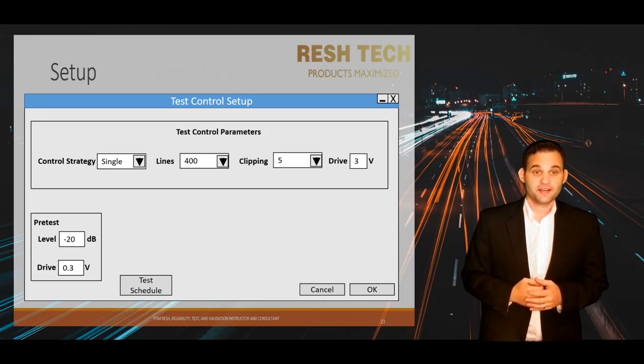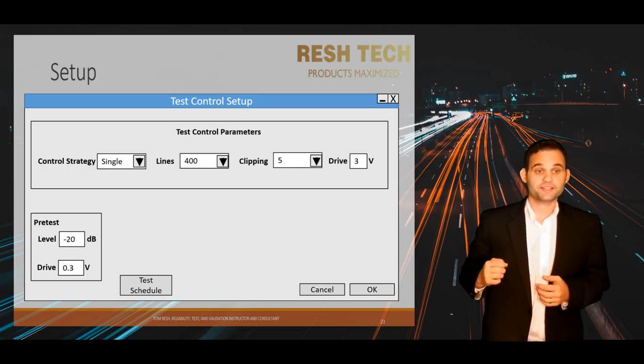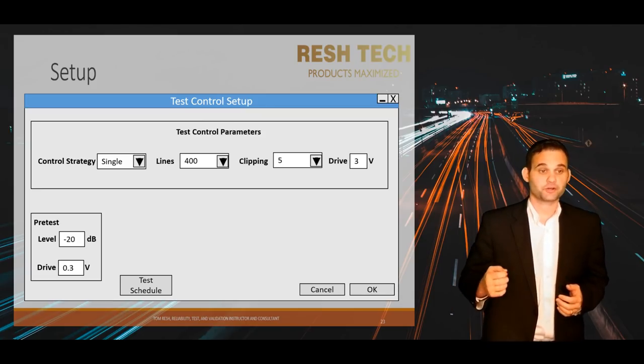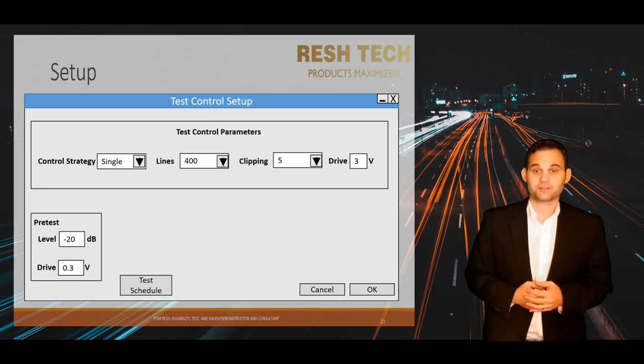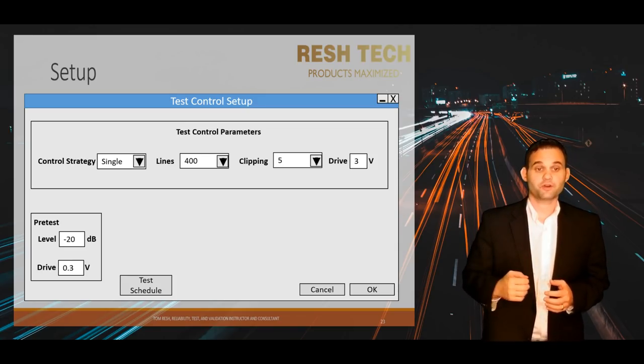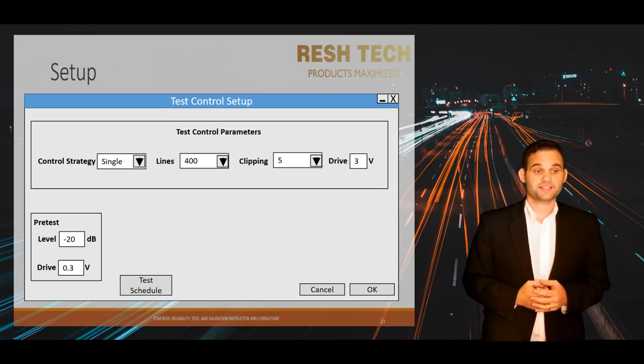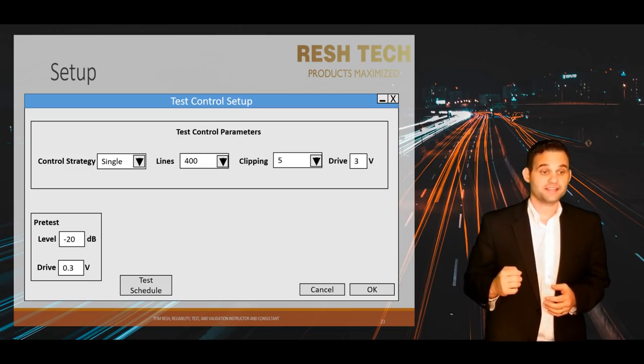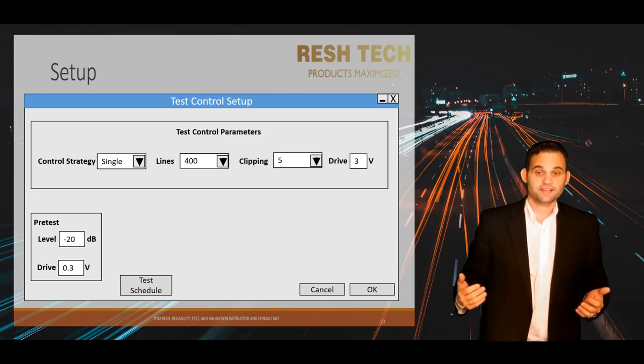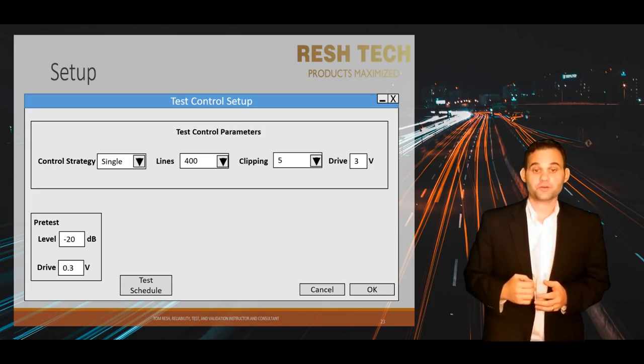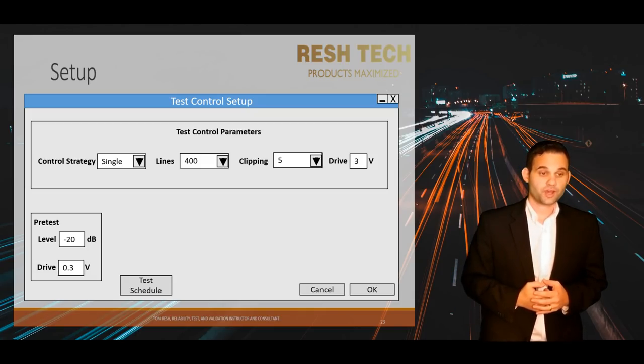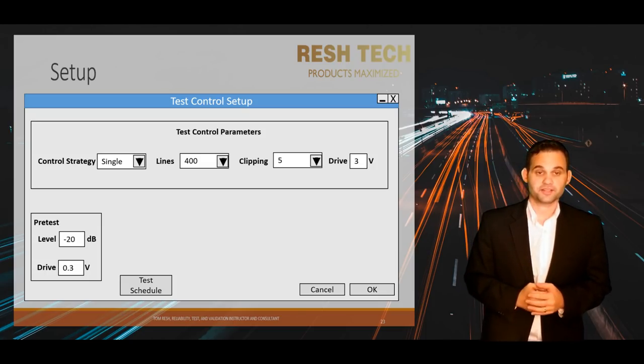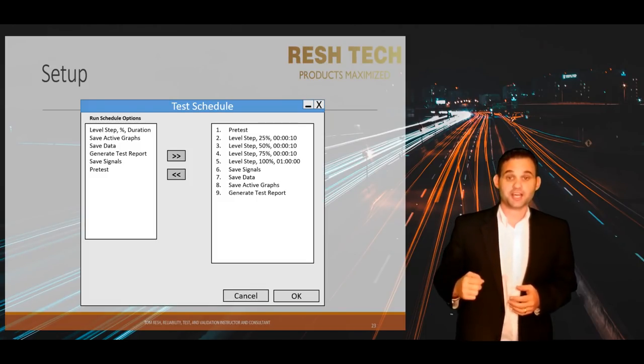Next are the pre-test settings. Sometimes you will see an option to enable or disable them. You want this setting enabled to catch mistakes like forgetting to attach your control accelerometer, torque your vibration fixture bolts, or torque your bullnose or drive cone bolts. Two common pre-test settings are your decibel ramp schedule, which lets your shaker run at a negative dB level from your test profile and slowly ramps up to ensure there are no issues with your control strategy or test setup. It can also be expressed as a percentage of your test profile levels.